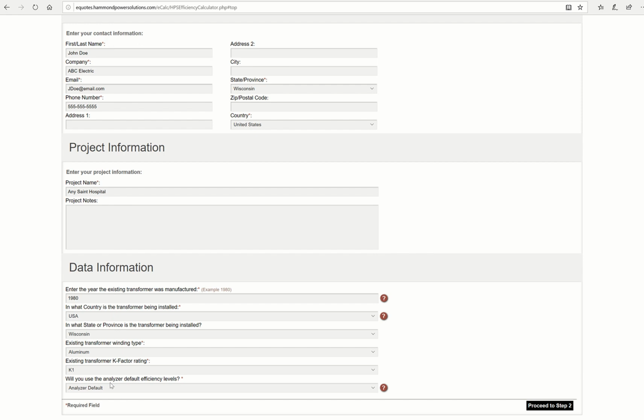In this case, we're also going to use the analyzer's default efficiency levels. While you can try to determine the efficiency levels of an installed transformer, none of that information is available on the nameplate or from the manufacturer for units built before 2007, and it's very difficult to get accurate efficiency levels when measuring a transformer in the field. So in this case, we're just going to use the analyzer's default values.